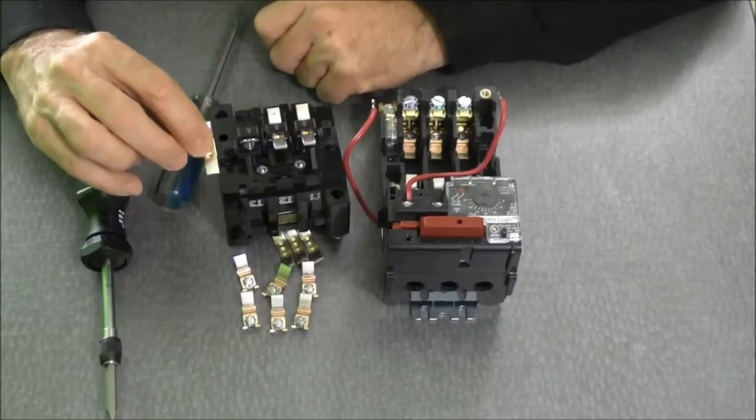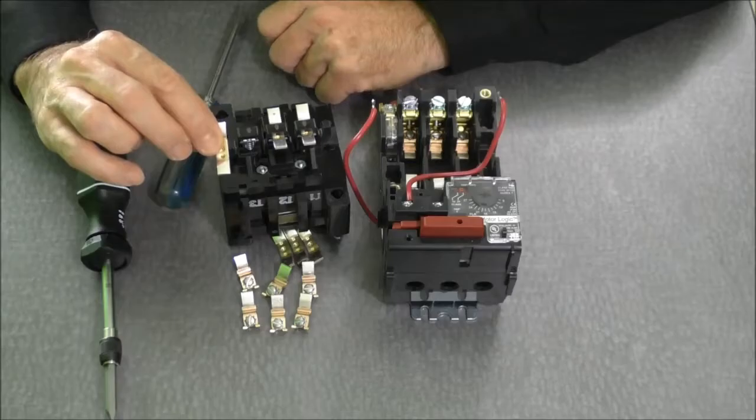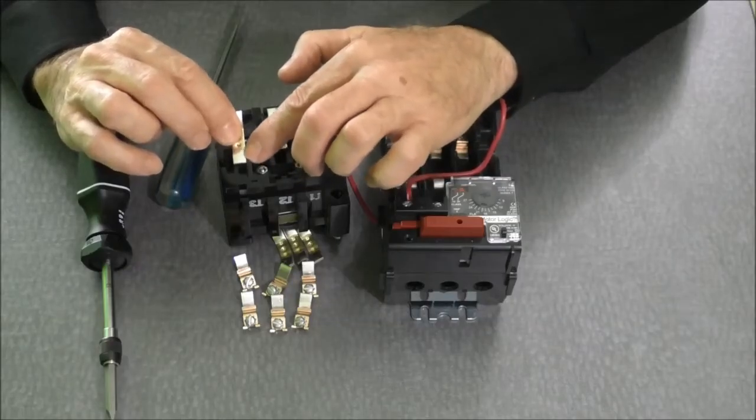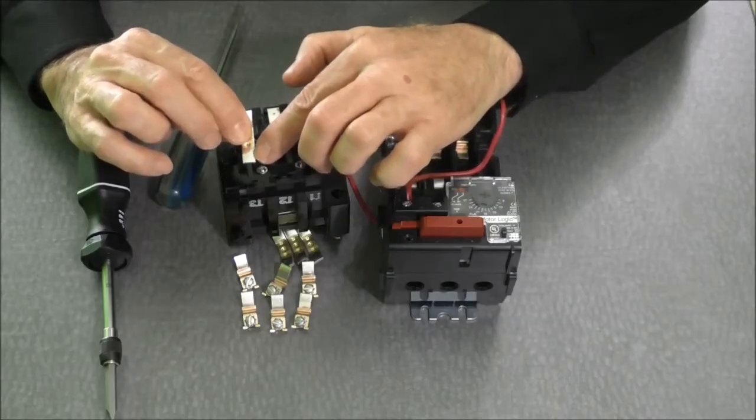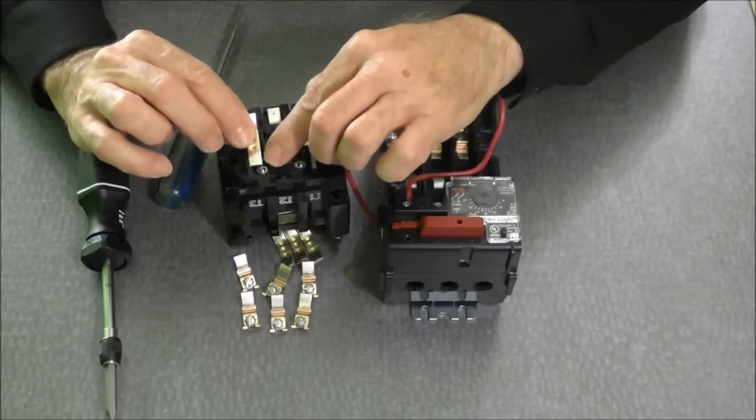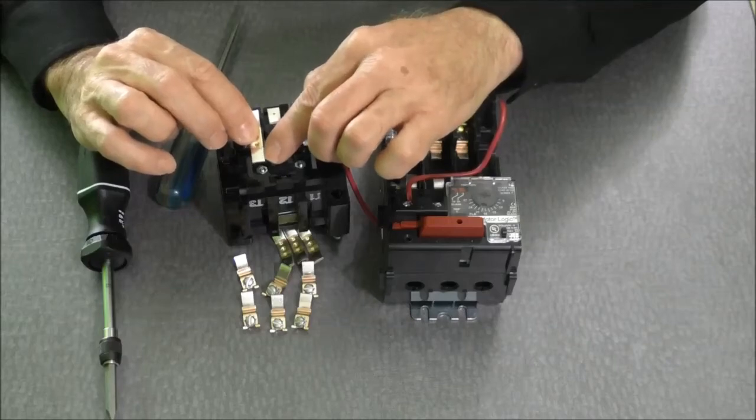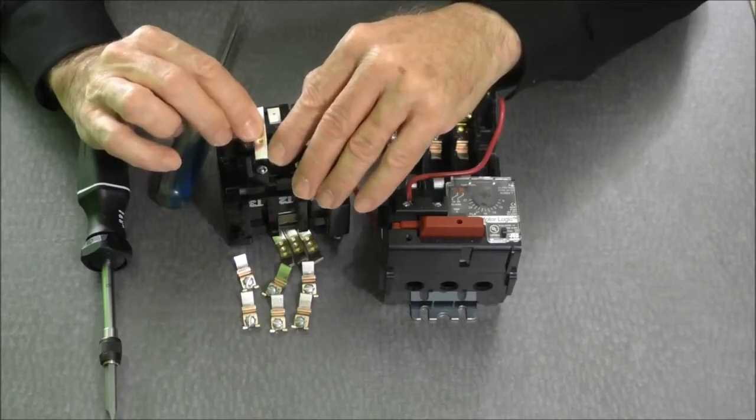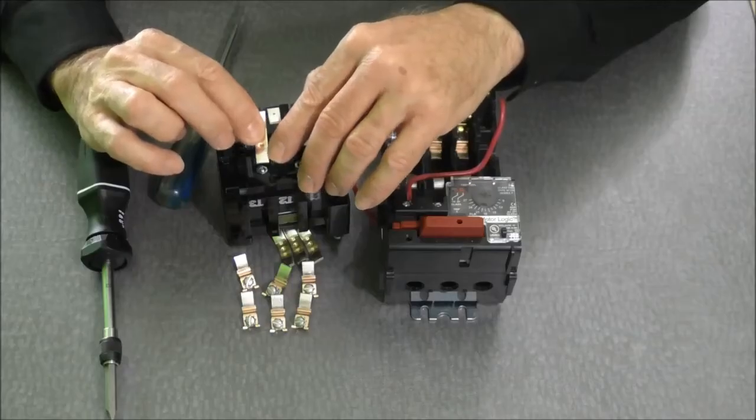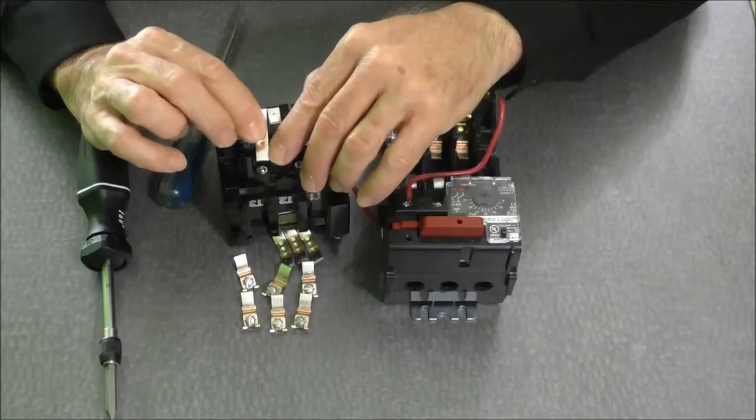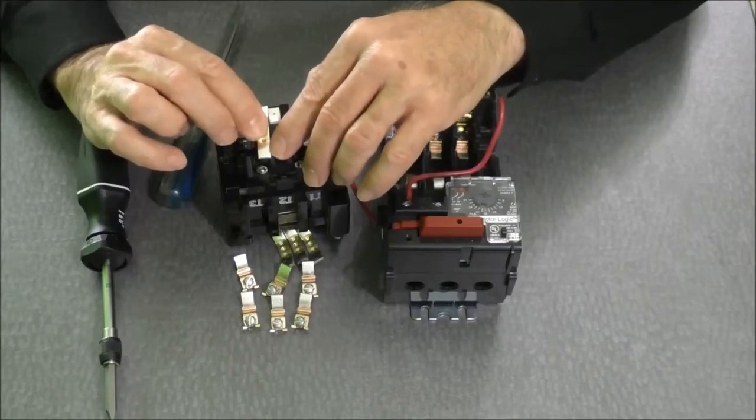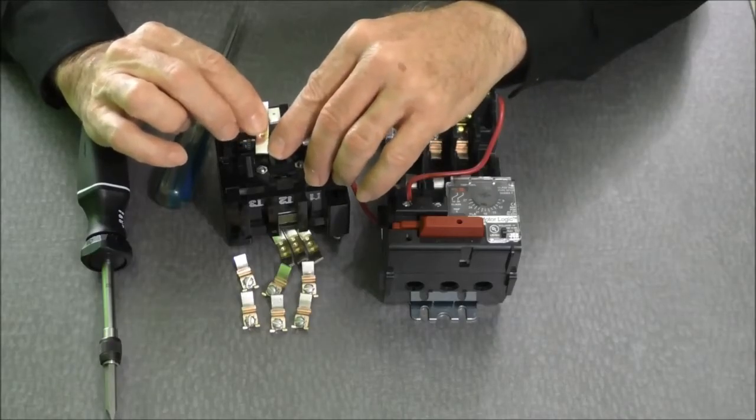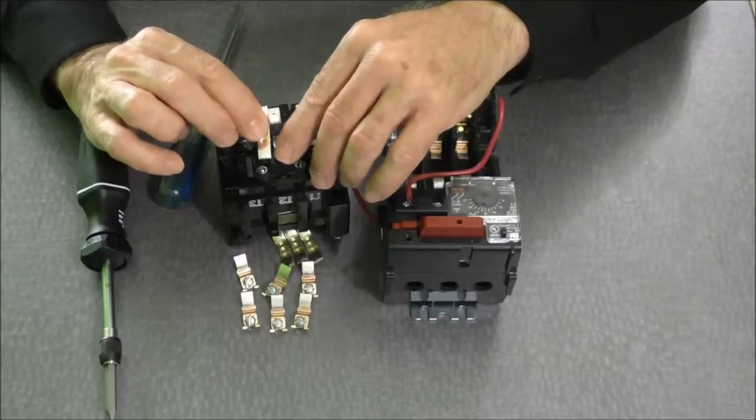These are new contacts. If these were used contacts we would have some pitting and scarring on this face. We would also have some black carbon on the contact surface. That is all perfectly natural. Every time this contactor opens and closes we have a little arc that's created. Every time we have a little arc we wear a little bit of the silver off the contact away. You should never try and polish a contact in a contactor. When you polish them or file them you're purely taking the silver off of the contact tips, removing life from those contacts.